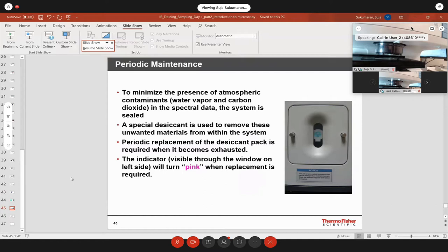The other question is like on a day-to-day basis, what needs to be turned off? I would say just turn the illumination lights off for the day, or just close down the software. But every time you close down the software, if you are doing individual spectrum collection, make sure you save all of them. So each of the spectra needs to be saved individually. The map, because you get the file name before you start your measurement, is saved automatically. But the spectra you individually need to save.